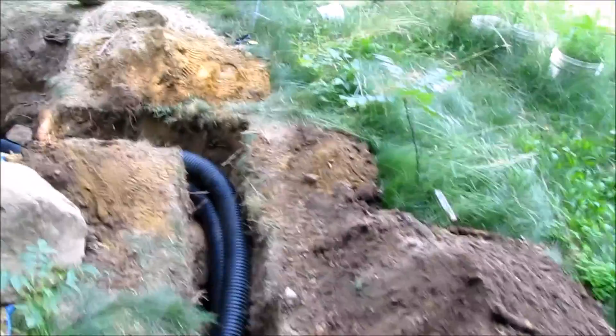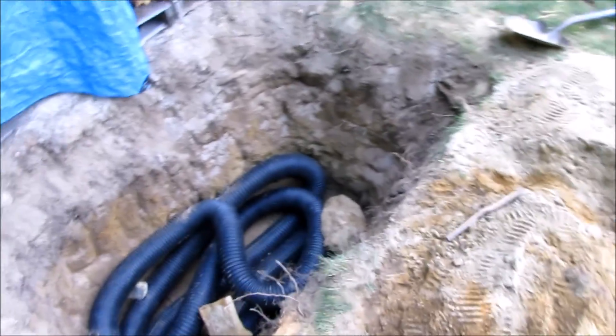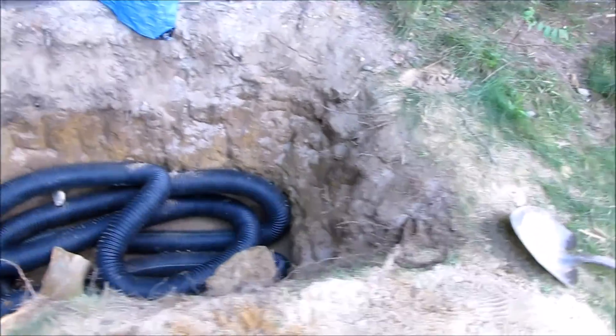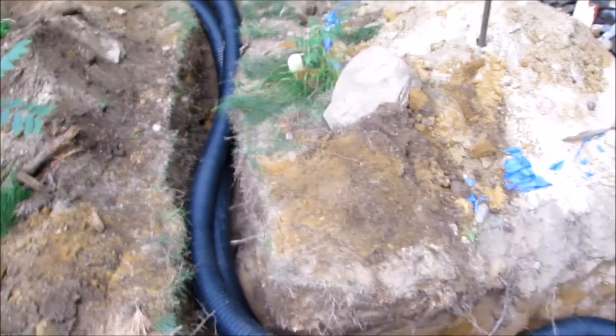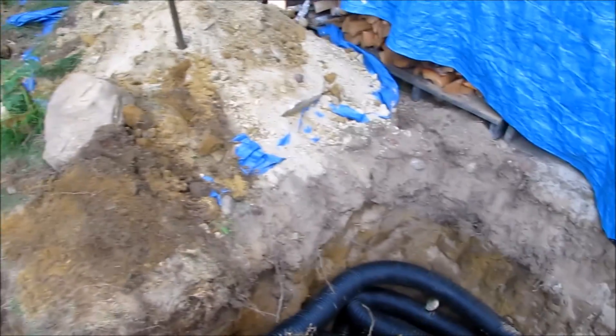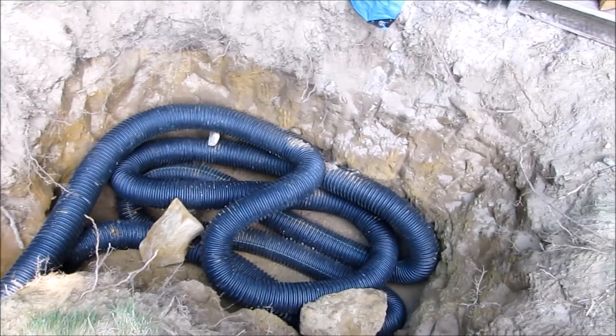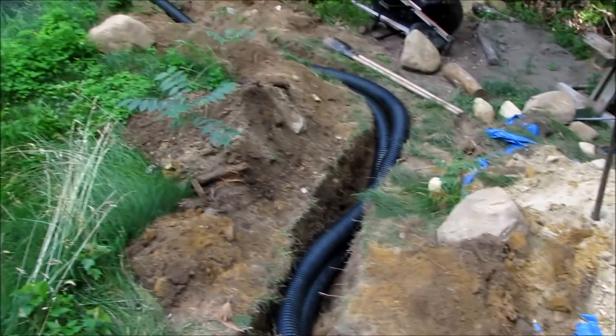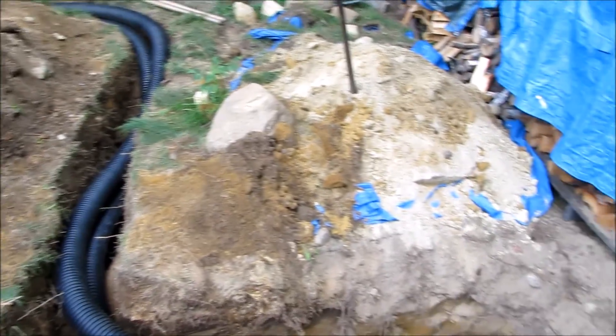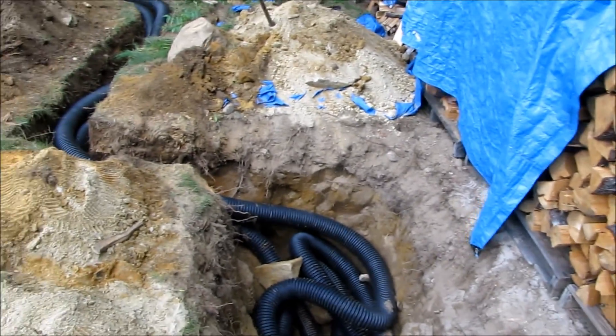I just have 4-inch diameter tubing here. I ran that from over there — the cold air from the greenhouse at night will blow in here with a fan, circulate through all these pipes down here — about 50 feet of pipe — and then come out the bottom line and go back into the greenhouse. It should be around 45 degrees at that point.